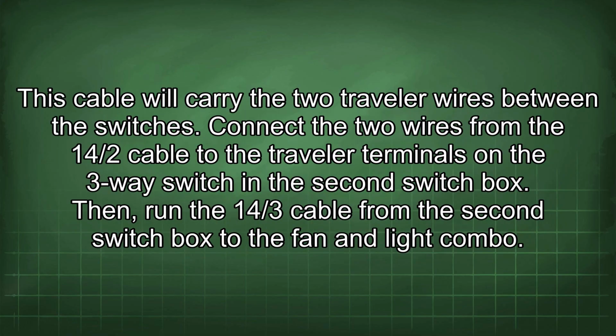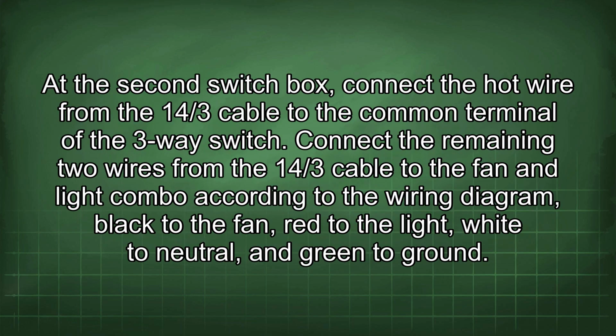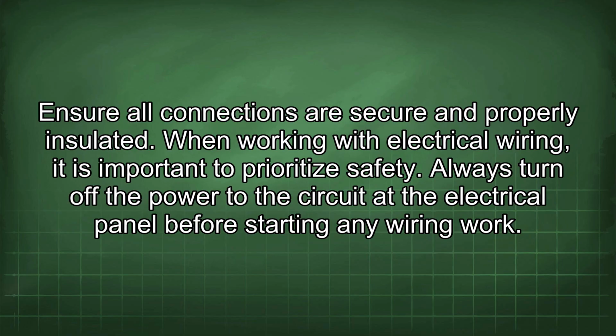This cable will carry the two traveler wires between the switches. Connect the two wires from the 14/2 cable to the traveler terminals on the three-way switch in the second switch box. Then run the 14/3 cable from the second switch box to the fan and light combo. At the second switch box, connect the hot wire from the 14/3 cable to the common terminal of the three-way switch. Connect the remaining two wires from the 14/3 cable to the fan and light combo according to the wiring diagram: black to the fan, red to the light, white to neutral, and green to ground. Ensure all connections are secure and properly insulated.